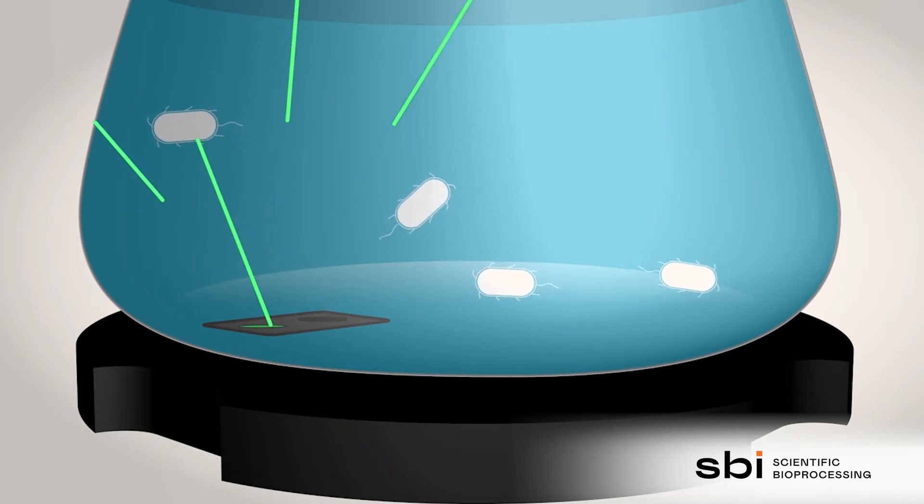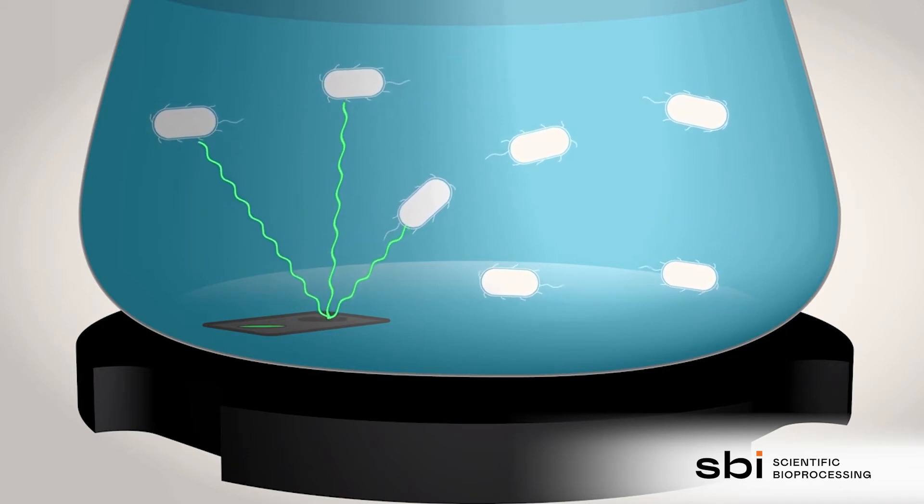The higher the concentration of microorganisms in the media, the higher the intensity of the backscattered light. This principle of measurement enables the CGQ to monitor the growth of the culture in real time.